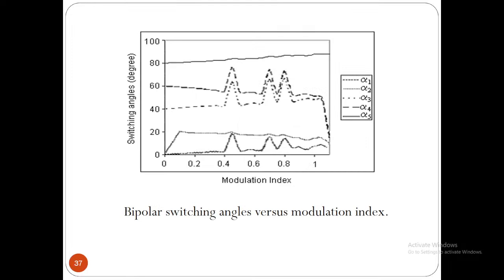So these are the switching patterns which are computed using this technique for bipolar switching. These are the 5 switching angles, which will be giving you individual harmonics less than 3% and total harmonics less than 5%. This is computed and you can go for switching at these angles—first quadrant switching angles.